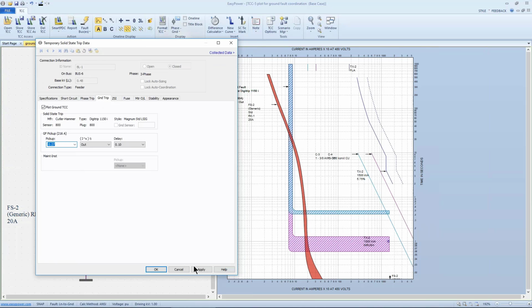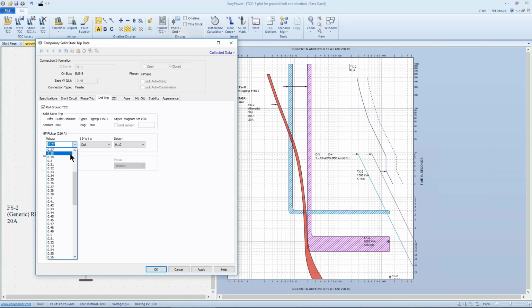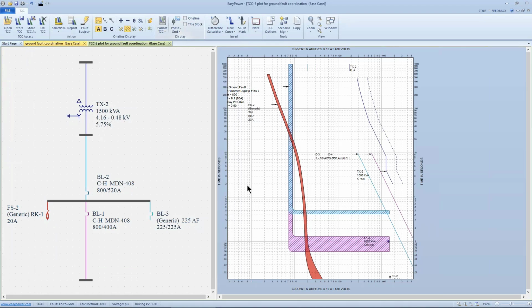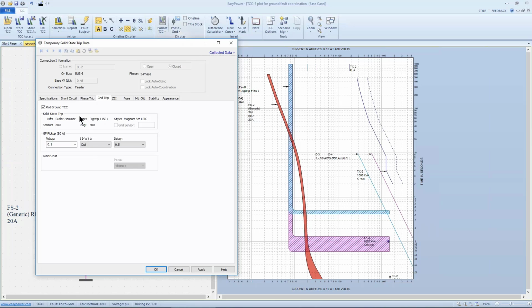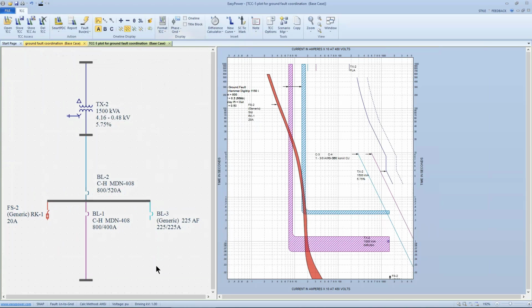If we set it higher, it would be less responsive, or it would respond at a higher current. So for the most part, we want to pick up as low as possible and as quick as possible. So the delay ranges from a tenth to a half a second. We'll go ahead and stay with the half a second. And what that tells us is the upstream one is set too low. So if we go to the upstream ground trip, we want to pick it up slightly higher, and it's already set at the longest delay. And so for coordination purposes, it would look like this.